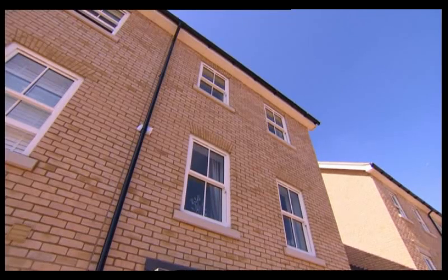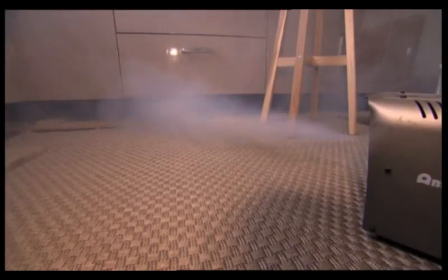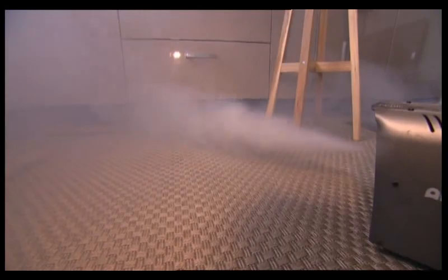My assessment is it's way below standard. You'll have a tremendous amount of heat loss, and fire precautions wise, very, very poor, because as we saw from the kitchen, smoke and the like spread straight out into your escape routes via the toilet. And that's totally unacceptable. You've got 2 floors above. How would they get out? Within 5 seconds, we had smoke coming through the roof.